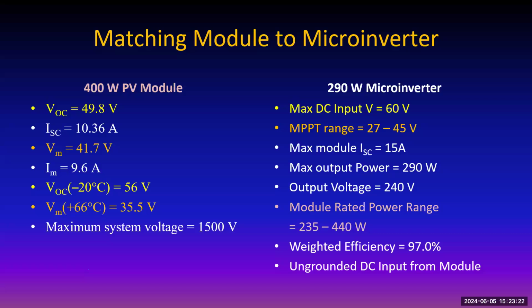The module has an output power of maybe 400 watts, and the module rated power range is 235 to 440, so the microinverter is happy with that as well. The weighted efficiency, meaning the efficiency of the microinverter under a range of different temperature and sunlight conditions, is 97%. And the only important thing here is the DC from the module to the microinverter cannot be grounded. It has to be an ungrounded system up there.